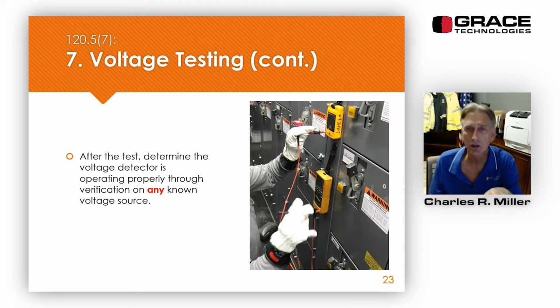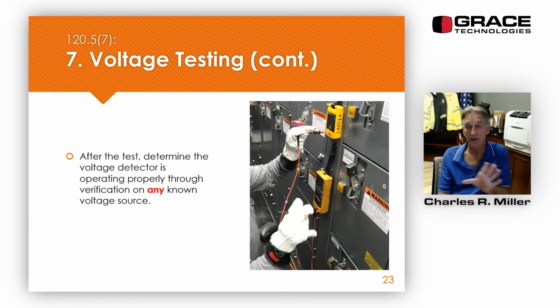You may have heard the term live, dead, live. I like that term. It's not in 70E. I like that term because if you can remember that, it's easier to catch that last testing of the meter. Because a lot of times, and I see this quite often when I'm doing hands-on training, someone will test the meter, they'll test for the absence of voltage, and bingo, they're done. Well, wait. And if they happen to look at me, they'll go, oh, and they'll remember at that point, oh, I gotta test the meter again.